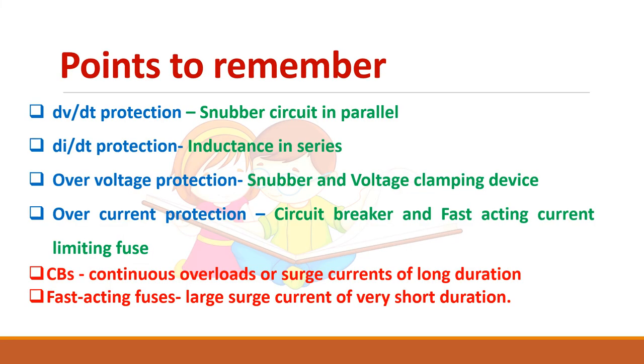Key points to remember: For dV/dt protection, use a snubber circuit in parallel. For dI/dt protection, use an inductance in series with the SCR. For overvoltage protection, you can use both a snubber and a varistor or voltage clamping device. For overcurrent protection, use a circuit breaker and fast acting current limiting fuse. Circuit breakers are used against continuous overloads of long duration; fast acting fuses are used for large surge currents of very short duration.